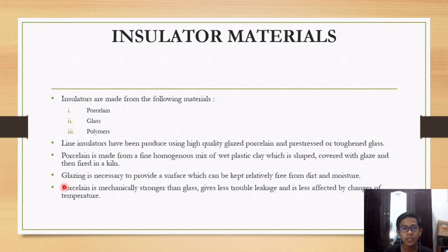Okay. Glazing is necessary to provide a surface which can be kept relatively free from dirt and moisture. Porcelain is mechanically stronger than glass, gives less leakage trouble, and is less affected by change of temperature.